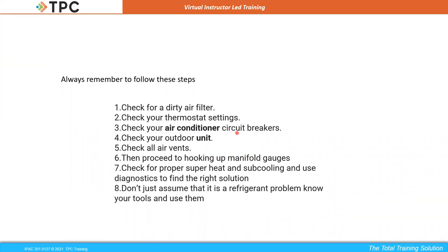Then, after you check these simple things, if you have a certification, remember EPA 608 says you have to have a certification to hook up your manifold gauges, check for proper superheat and subcooling, and use diagnostics to find the right solution. And don't always assume it's a refrigerant problem. Know your tools and use them. Just because you think it's low on charge, it could actually be a dirty air filter making it look like it's low on charge.